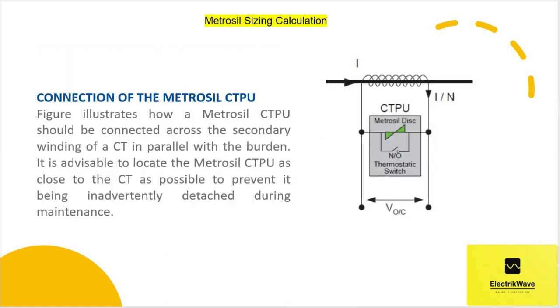Next. Here you can see connection of the Metrosil CTPU. Figure illustrates how a Metrosil CTPU should be connected across the secondary winding of a CT in parallel with the burden. It is advisable to locate the Metrosil CTPU as close to the CT as possible to prevent it being inadvertently detached during maintenance.